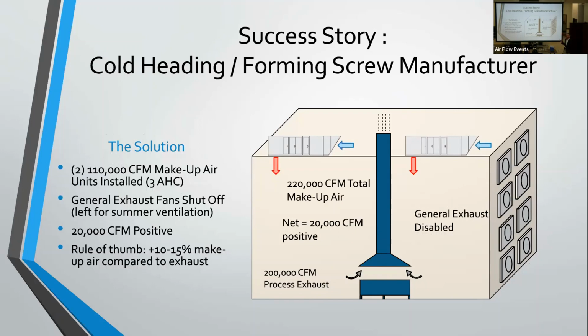They not only installed the makeup air units, they actually recommended turning the general exhaust fans off, because you're not allowing the process exhaust systems to do their job when you're creating that negative pressure by trying to pull that air out. So basically, let your process exhaust do its job. Give it the air that it needs with the makeup air units, and the problem should resolve itself.